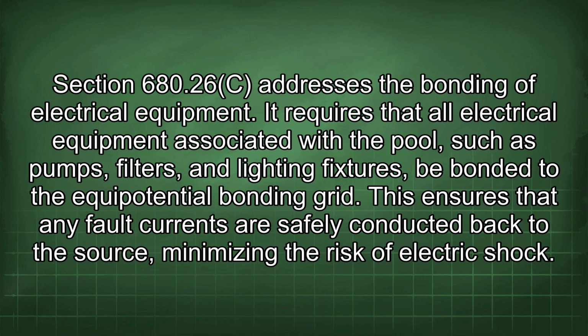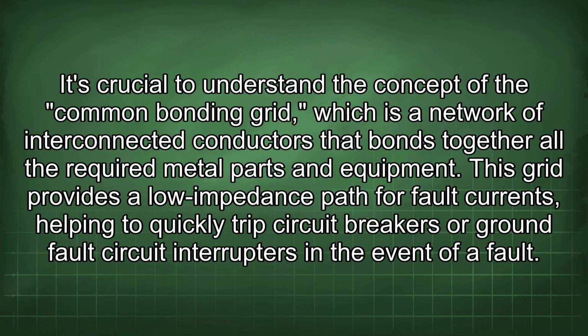This ensures that any fault currents are safely conducted back to the source, minimizing the risk of electric shock. It's crucial to understand the concept of the common bonding grid, which is a network of interconnected conductors that bonds together all the required metal parts and equipment. This grid provides a low impedance path for fault currents, helping to quickly trip circuit breakers or ground fault circuit interrupters in the event of a fault.